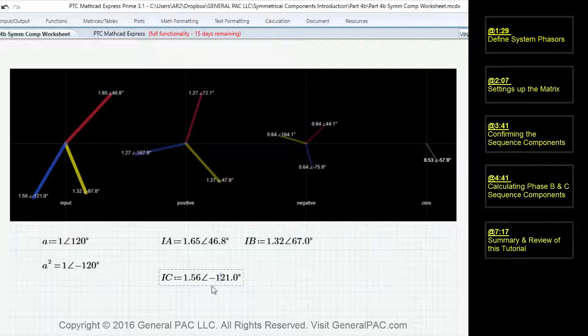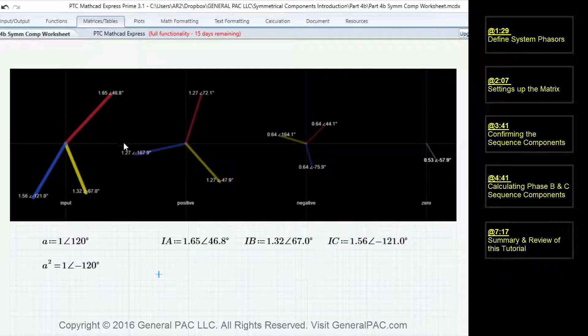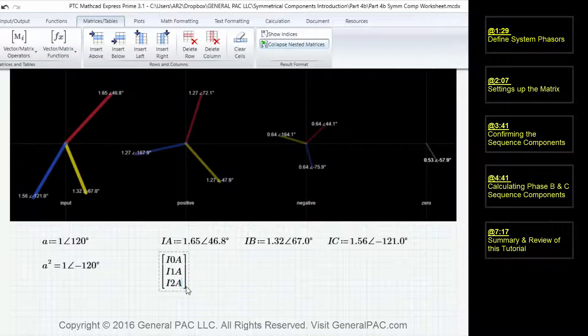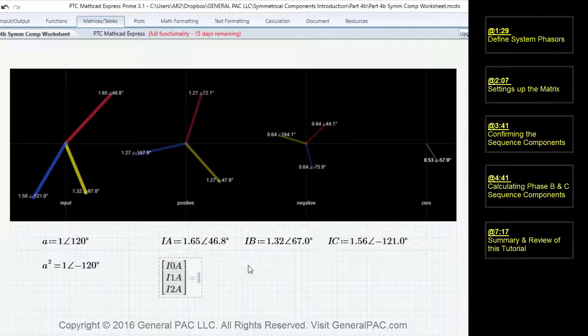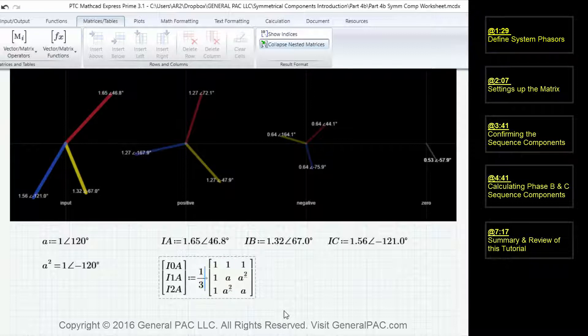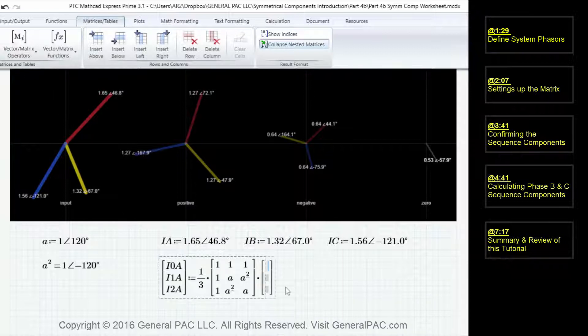I'm going to rearrange this so we have more room to work with. In Part 4, we learned the matrix to calculate the positive, negative, and zero sequence components based off the system phasors. We're going to input a 3-by-1 matrix — the zero sequence component, the positive sequence component, and the negative sequence component for phase A — equal to one-third times the 3-by-3 A-inverse matrix, multiplied by the system phasors IA, IB, and IC.